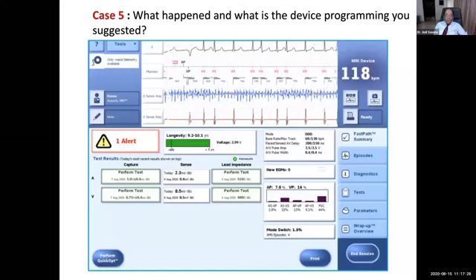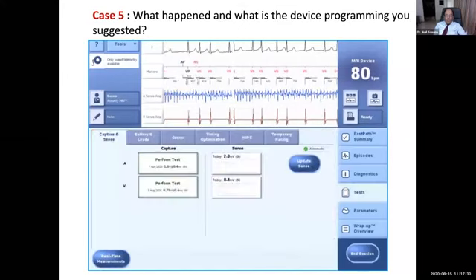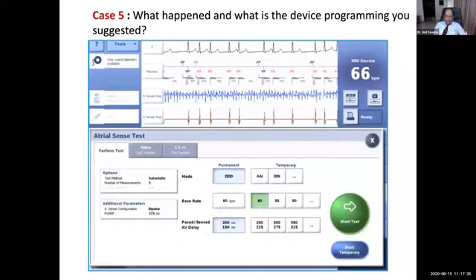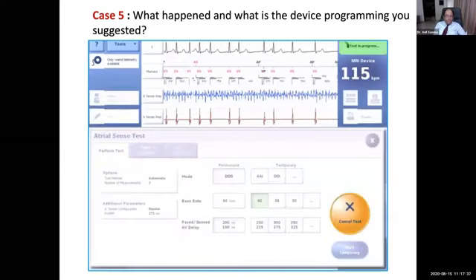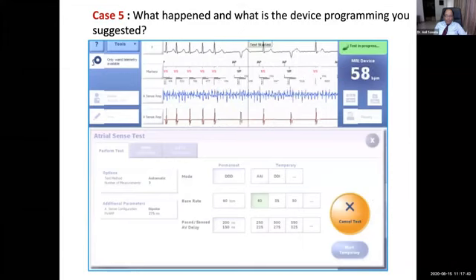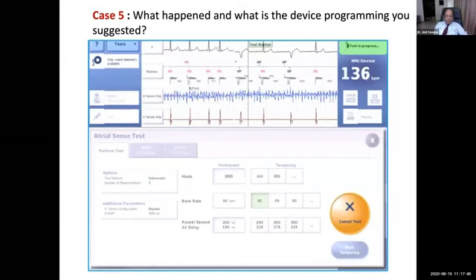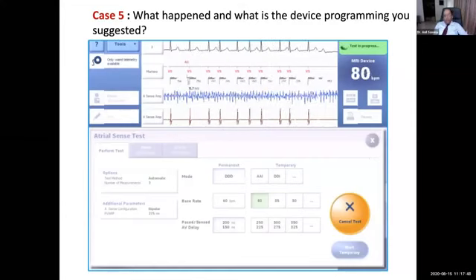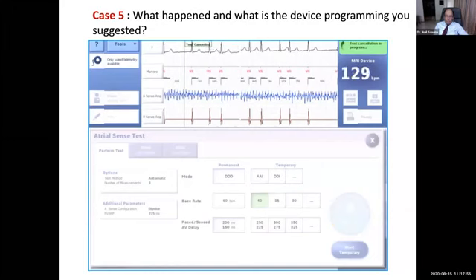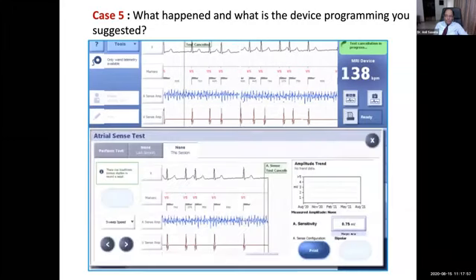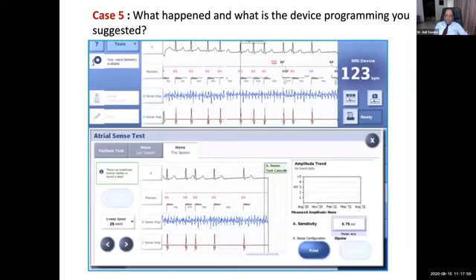Now that's the video of this patient, and we can see that the rhythm that is going on is atrial fibrillation as shown in the atrial channel. So we want to measure the P wave here, and we start the atrial sense test. But the problem is that if you start the atrial sense test just like that in the automatic mode, it will start from the currently programmed sensitivity, which was 0.75. So it's not sensing any P wave because the starting sensitivity was too low. So we stop the test.